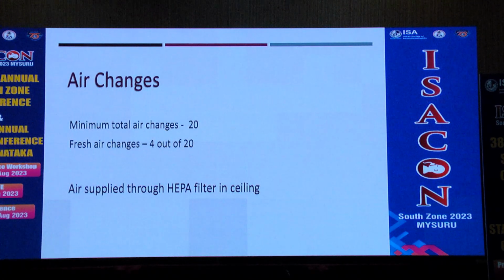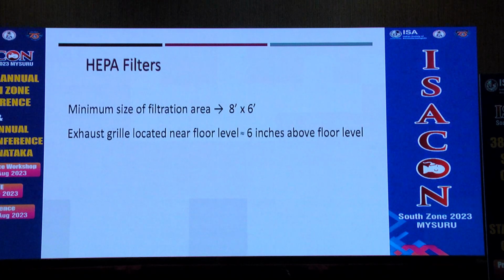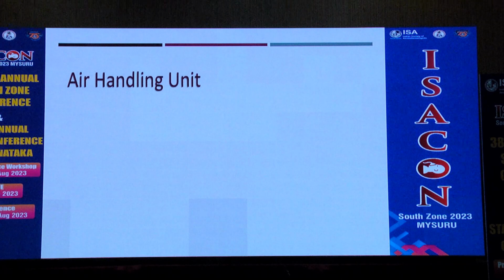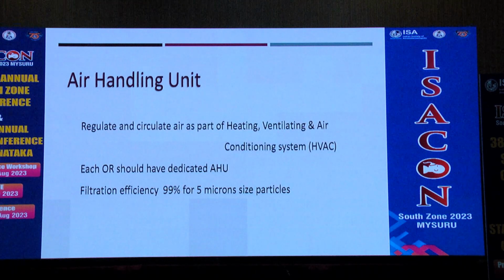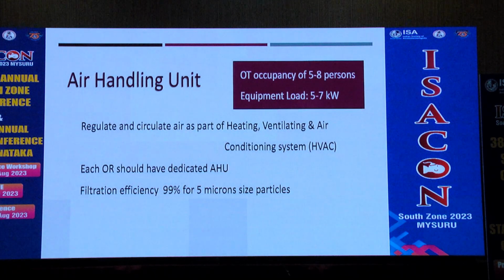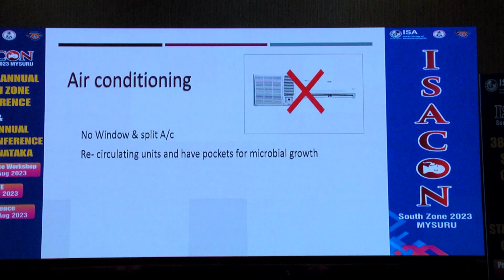There should be a minimum total of 20 air changes, of which at least 4 should be fresh air changes. It should be supplied through HEPA filters. There are sizes for this. That is called the air handling unit. Each OR should have a dedicated air handling unit, with a filtration efficiency of at least 99% for particles of size 5 microns, and each OT should have an occupancy of 5 to 8 persons. There should not be any split AC or windows, because they are recirculating units and pockets for microorganism growth.